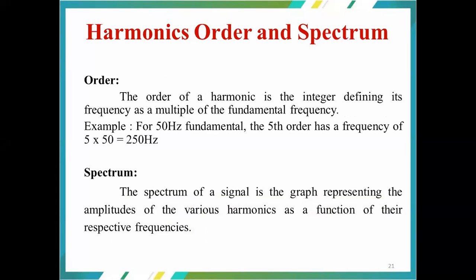So order means an integer defining its frequency as a multiple of the fundamental frequency. So the fundamental component means 50 Hertz in India, and fifth order means 250 Hertz, that is the product of five and the fundamental frequency. So the spectrum of a signal is the graph representing the amplitudes of various harmonics as a function of their respective frequencies.